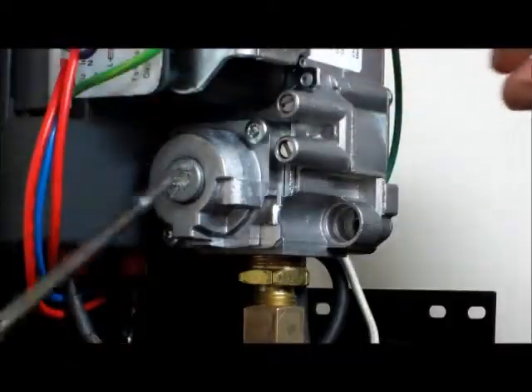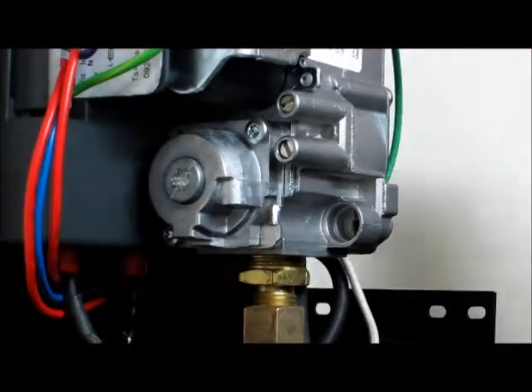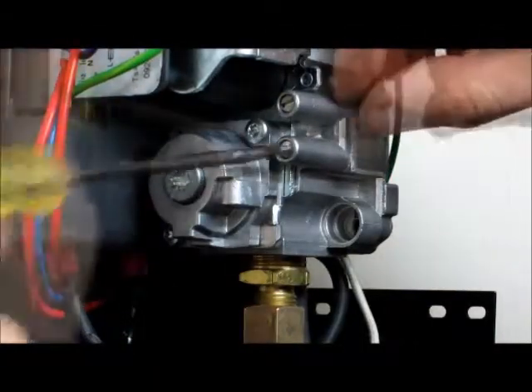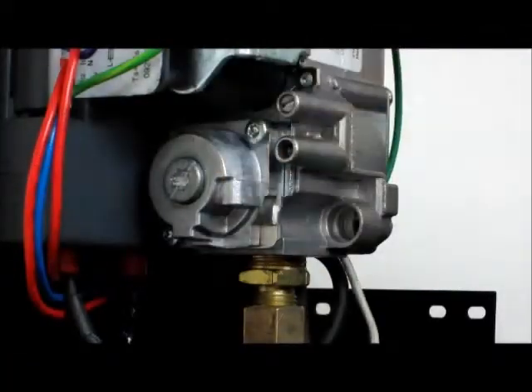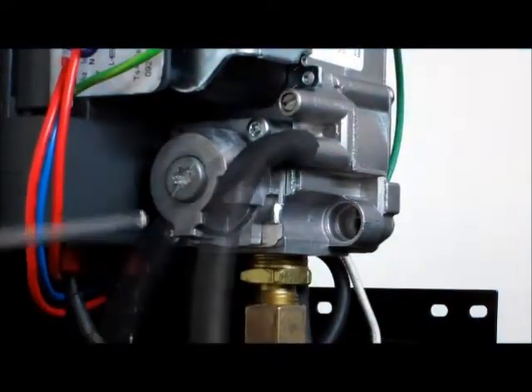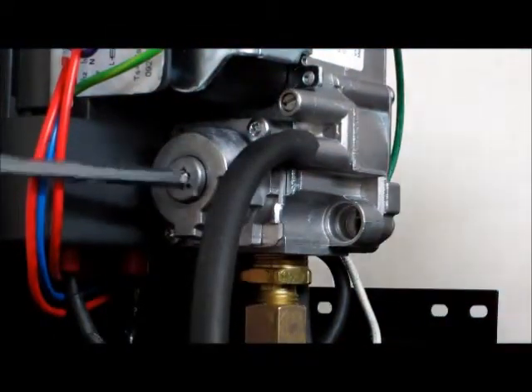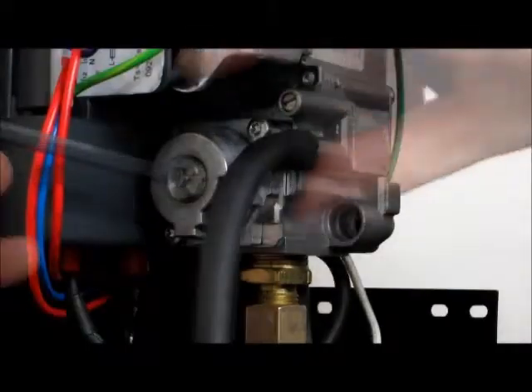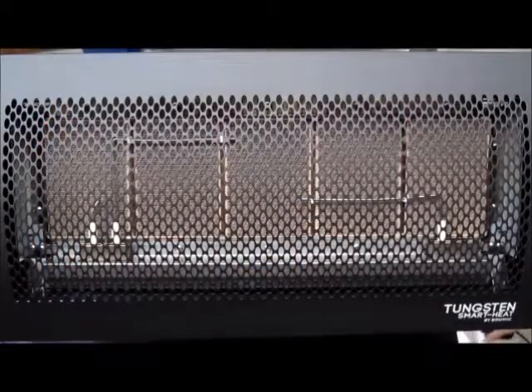If gas flow is as specified and the heater is still not starting, the gas valve must be checked. This can be achieved by testing the outlet pressure test point and ensuring gas begins to flow upon powering up the unit. If the unit is powered up and the regulator adjustment wound down and no gas flow is occurring, inform your dealer and organize a replacement valve.